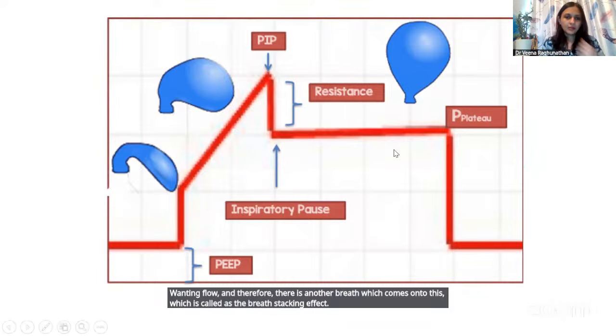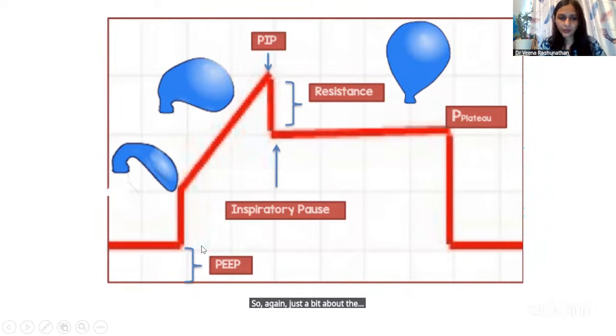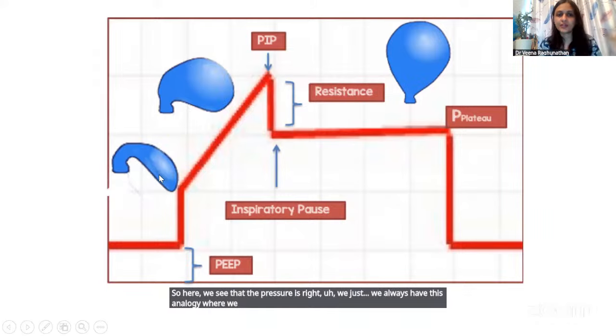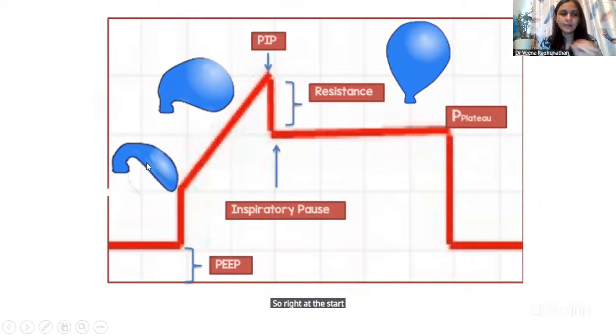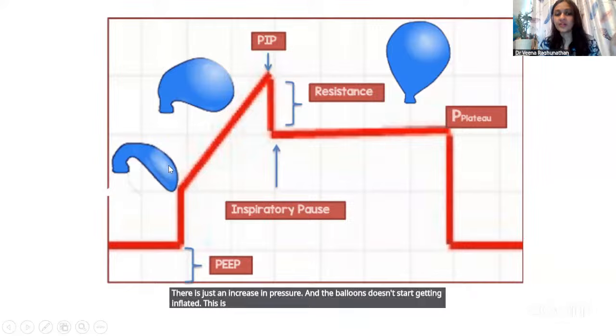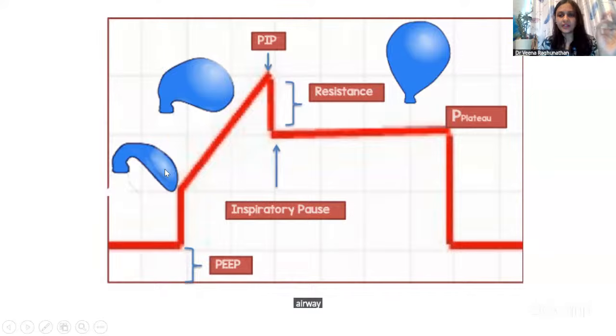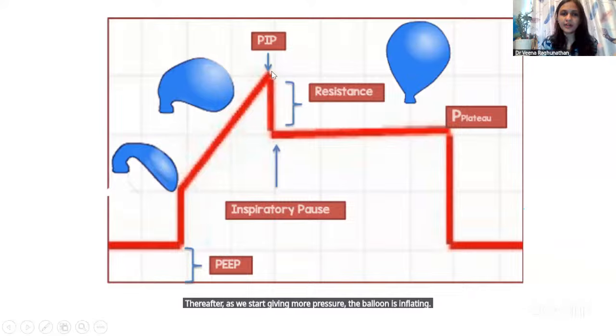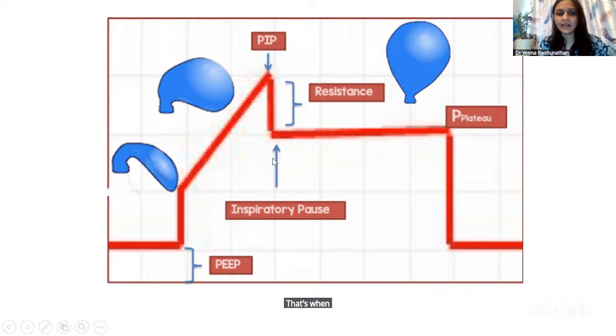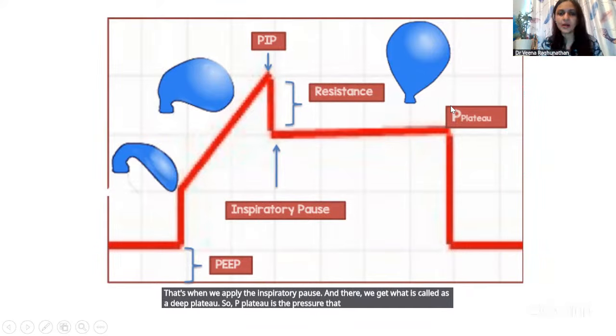So again, just a bit about the inspiratory hold. Here we see that the pressure is rising. We always have this analogy where we compare it to the inflation of a balloon. Right at the start, when we start blowing into a balloon, there is just an increase in pressure and the balloon doesn't start getting inflated. This is to overcome the resistance of the airway right till we reach up to the lung. Thereafter, as we start giving more pressure, the balloon is inflating till the point we reach the PIP. After that, when we close the balloon, that's when the pressure inside slightly reduces. That's when we apply the inspiratory pause, and there we get what is called the P plateau. So P plateau is the pressure that is required to keep the lung open.